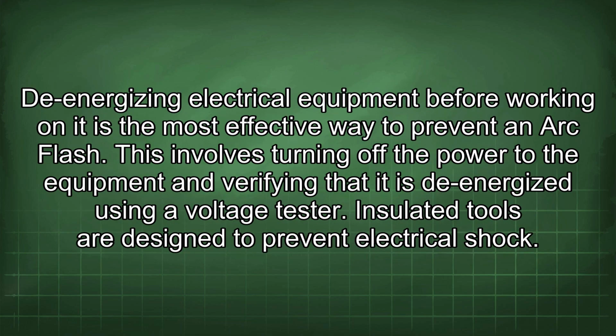De-energizing electrical equipment before working on it is the most effective way to prevent an arc flash. This involves turning off the power to the equipment and verifying that it is de-energized using a voltage tester.